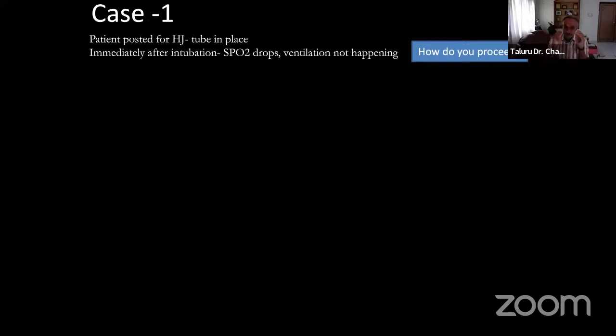There is one safety mechanism in the ventilator. Whenever pressure goes up, there is a safety valve. What is that valve? I've told you many times. You remember now. Now I have made you wait. Whenever a patient goes into a spasm, the Pmax setting would normally be around 30, 25 because we are ventilating a normal patient. If the PIP goes to 30, 40, 45 because the patient has gone into a spasm, more pressure going into the patient will start going out because the Pmax setting is at 30. So the first thing you have to do is increase the Pmax setting.